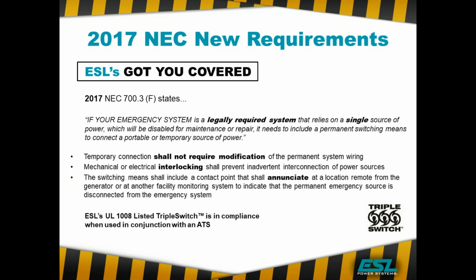So as we're talking about permanent generators, not only is load bank testing and some of the requirements there important, there's the NEC 2017 700.3(F) code that talks about backing up permanent generators. This code is written so that if a system is legally required single source of power and it becomes disabled for maintenance or repair, you must provide some means to back up that permanent generator with temporary power. So the question here is what's legally required?